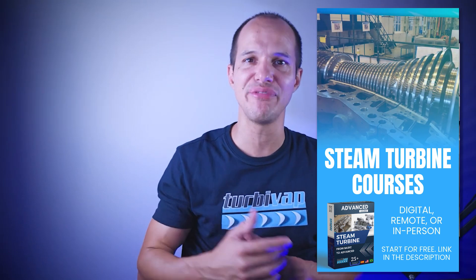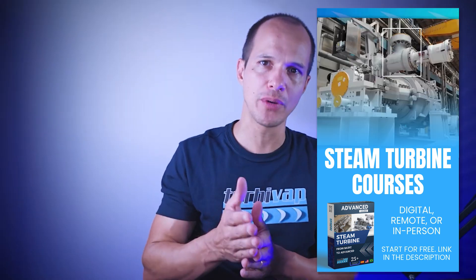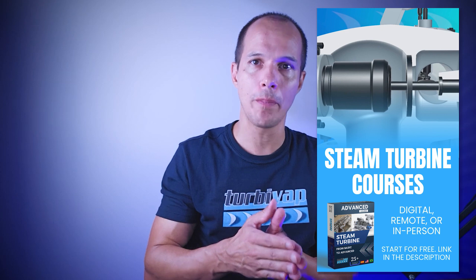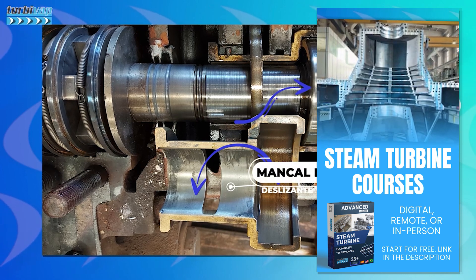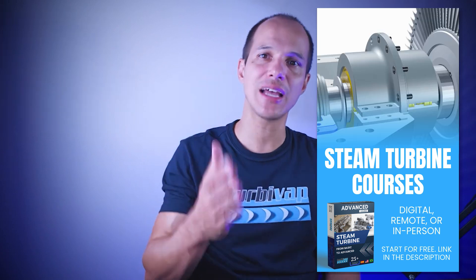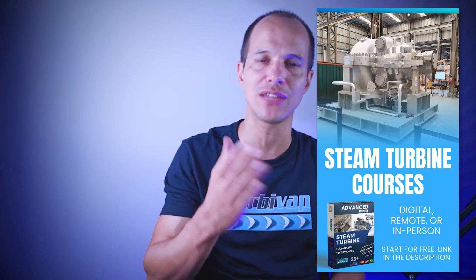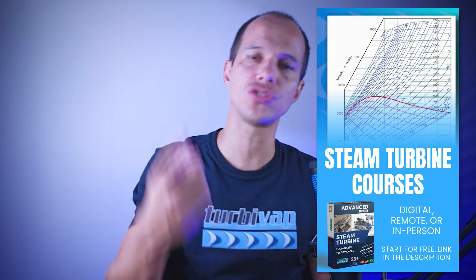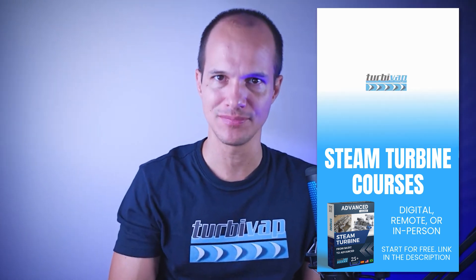The plane bearing is coated with the famous babbitt metal — I'll leave a playlist card for you to check out the topic about bearings. Just to clarify: the axial bearing should not be confused with the radial bearing. There are still low power turbines which operate with babbitt plane bearings fulfilling the radial function and a bearing fulfilling the axial function. It is exclusive to low power, low speed turbines, and it is exactly in these cases where oil rings are usually applied for lubrication.